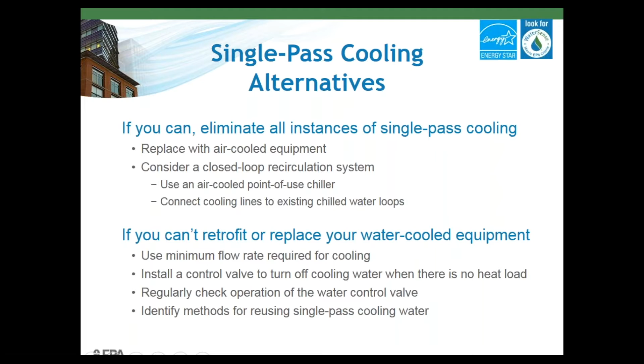In cases where you can't eliminate single-pass water use, make sure you're using the absolute minimum quantity needed. Check the equipment specifications and make sure the maximum temperature rise in water is happening, and that will help minimize your water use as well. Also, make sure the water is controlled with the motor or compressor so it'll turn off when it's not running, so you can't use or waste any extra water.